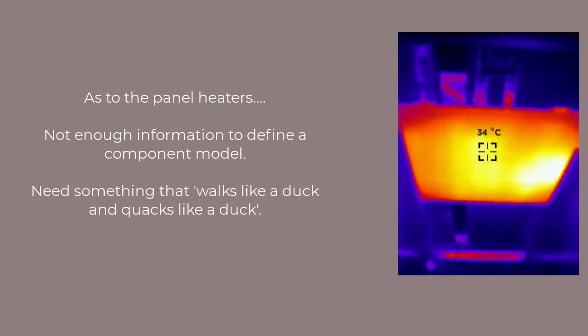About the ceiling heaters. I wasn't able to get everything I needed in order to set up the panels as detailed components. Perhaps detailed components are an overkill. The critical attributes were response time and surface temperature, as well as the ability to distribute heat properly within the space. What I chose to do is create a heating panel that's really a thin bounded zone, into which I'm going to inject some heat.